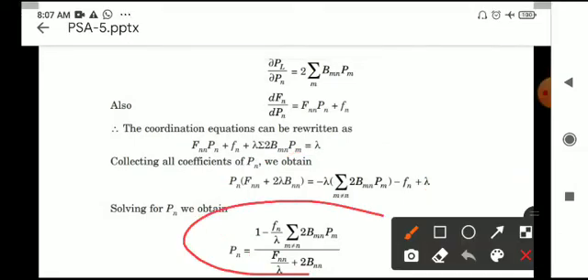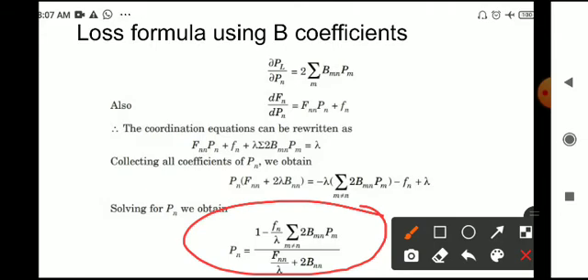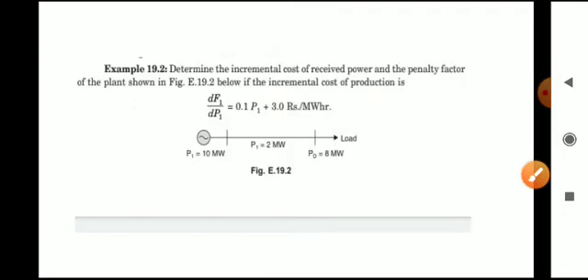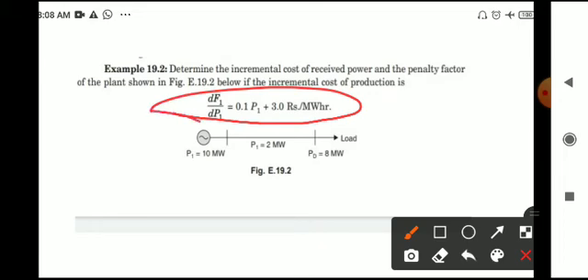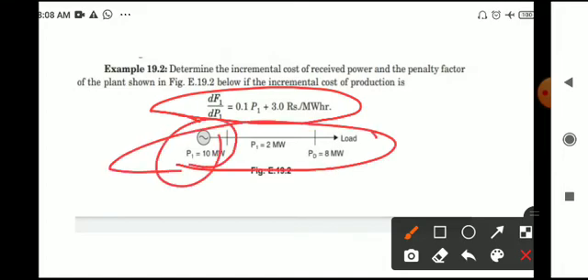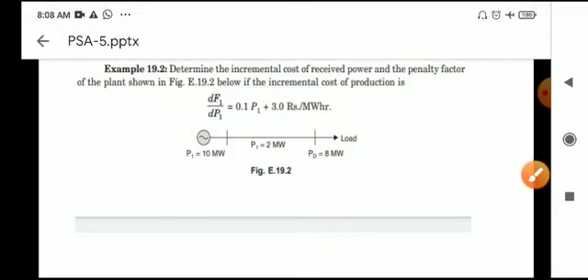This equation is used in the iterative method for economic load dispatch including losses, as discussed in previous lectures. This is the loss formula using B coefficients. Now we are doing a problem based on the penalty factor: determine the incremental cost of received power and the penalty factor of the plant shown in the figure below, if the incremental cost of production dF1/dP1 equals 0.1·P1 plus 3 rupees per megawatt-hour. From the figure, the plant produces 10 MW, 8 MW is delivered, and 2 MW are losses.